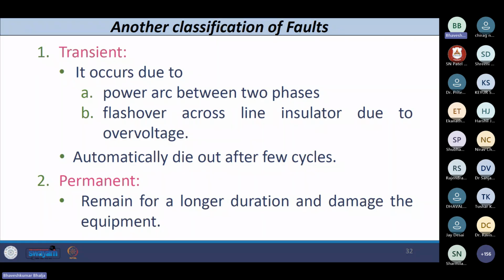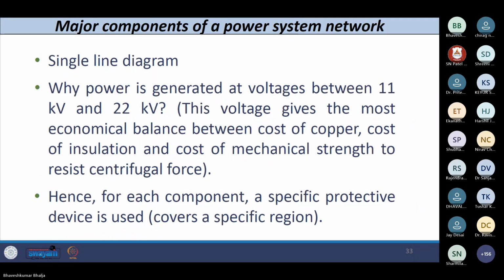That means the fault occurs and dies out after several cycles, maybe 1 cycle, 2 cycles, 3 cycles, depending upon the severity of the fault and other operating conditions. Hardly 20% or 10% of faults are permanent in nature, which last for a longer duration. That may damage your equipment, and the utility has a mechanism to detect and isolate through the circuit breaker whenever such a permanent fault occurs.